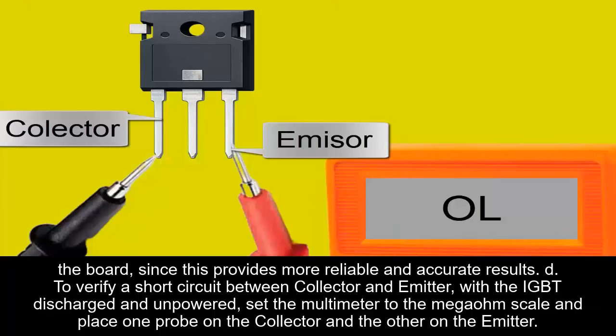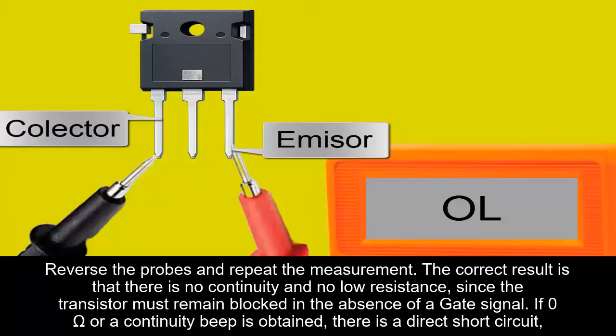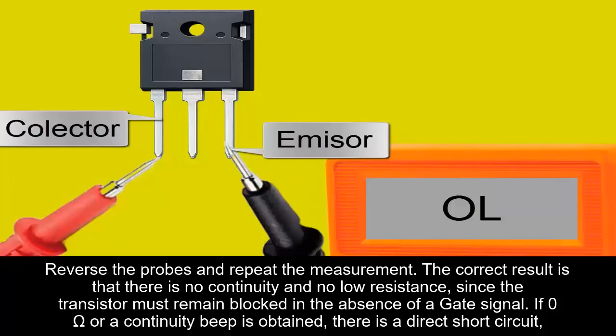D. To verify a short circuit between collector and emitter, with the IGBT discharged and unpowered, set the multimeter to the megaohm scale and place one probe on the collector and the other on the emitter. Reverse the probes and repeat the measurement. The correct result is that there is no continuity and no low resistance, since the transistor must remain blocked in the absence of a gate signal.